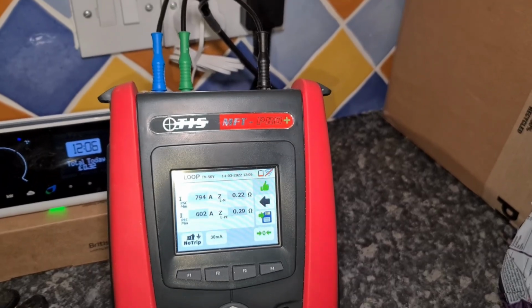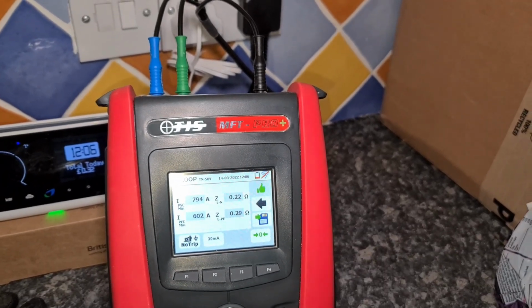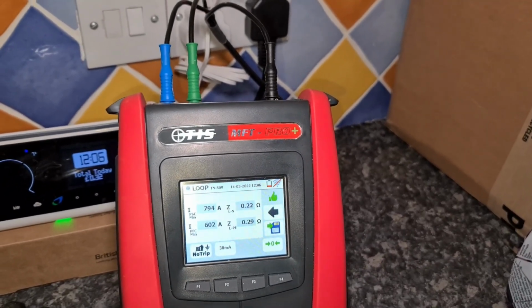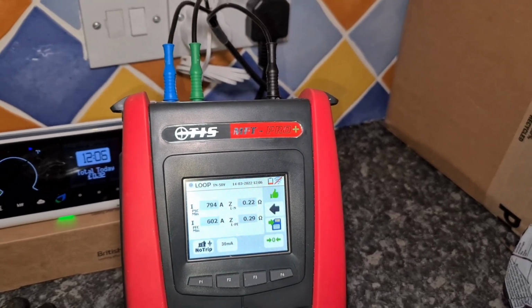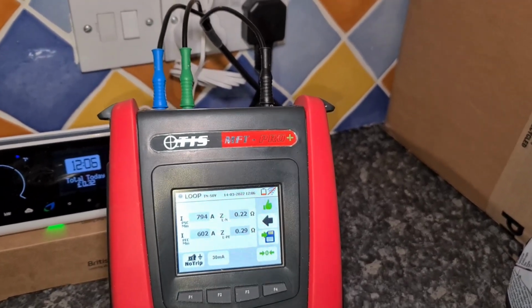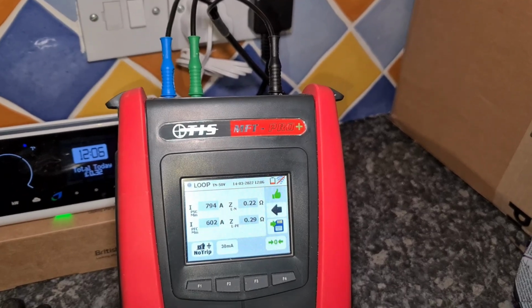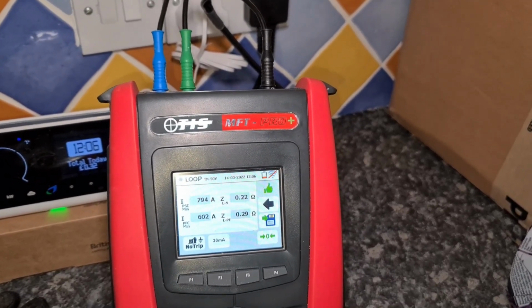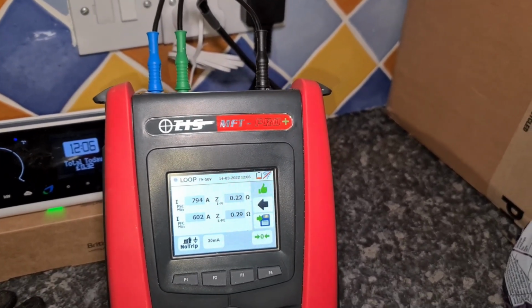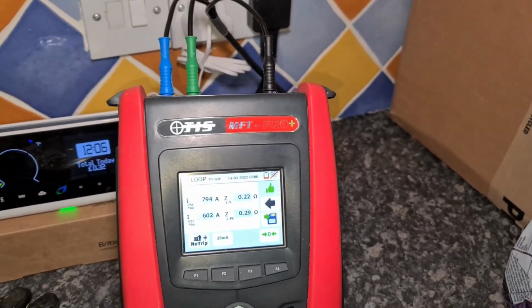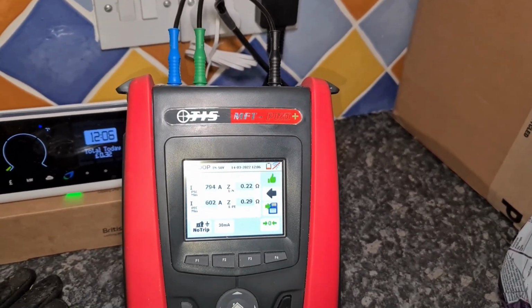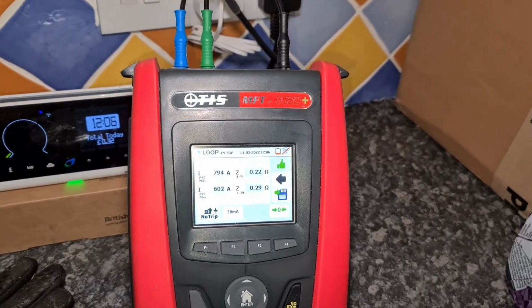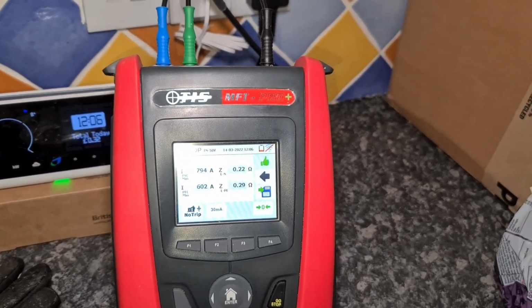It can, in some cases, be reading lower than the true impedance path, and that can be due to a high resistance point through an MCB, for example. There was a big garage fire shown in one of my YouTube videos that showed exactly that, and that was due to a high impedance MCB. But we'll move on and we'll get some Zs measurements at a light fitting.